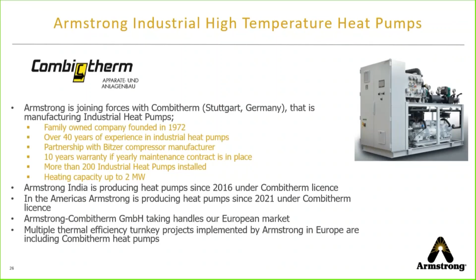So, heat pump basics. What are heat pumps? They really use the reverse refrigeration principle to recover low-grade heat and generate higher-grade heat, typically hot water and cooling water for our processes. Typical heat pump COP, or coefficient of performance, ranges from 2 to 7. The higher the COP, the better the return. And we're using electricity, green electricity where available, into the heat pump to take that low-grade heat and generate the higher-grade thermal energy out.